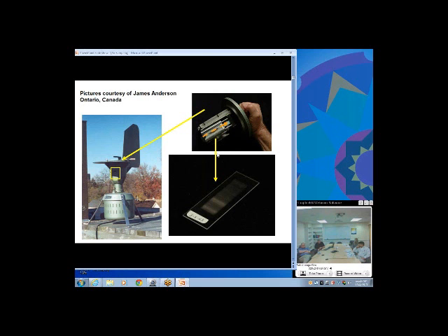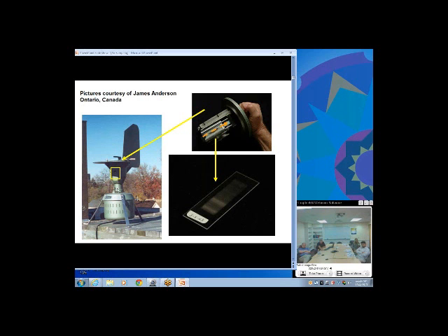This is a spore trap as manufactured by Burkard, which is what we have on the roof of the hospital. The vacuum fan is a series of tubes that spin on a plate, and a vacuum is pulled in the center. Depending on the quality of the seal, the vacuum is good or bad — we've had to replace the seal before. We check the flow rate about monthly to make sure it's within specifications.